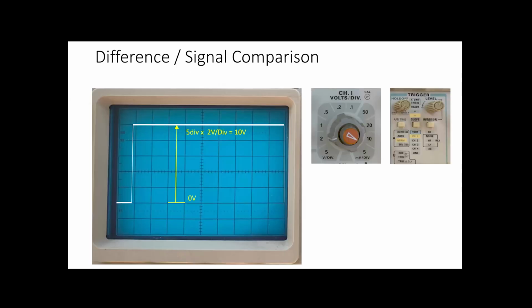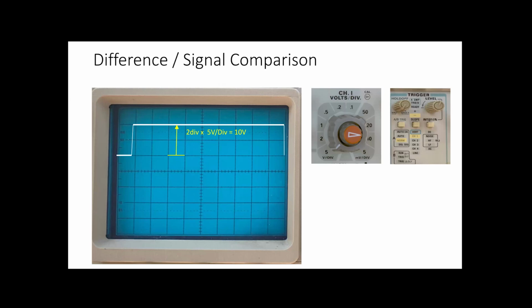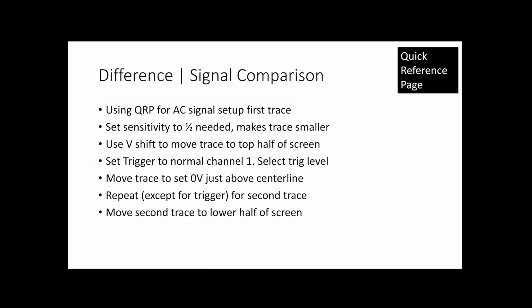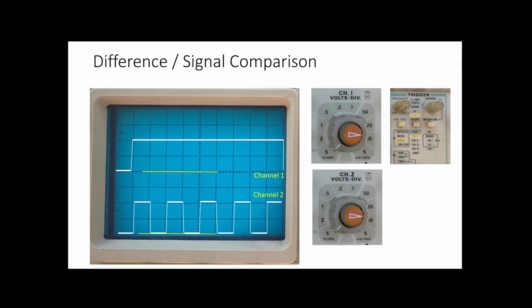Notice the volts per division, instead of being 2 volts per division, I'll turn it to 5 volts per division. And once I've turned it to 5 volts per division, I can move the picture up to the top of the screen. Once I've done that, I can then switch on the second trace. I can set my 0 volts as I did before, just below the centre line this time. I don't trigger it on the second trace, I trigger it on the first trace. So there we are, I'm still triggered on the first trace.